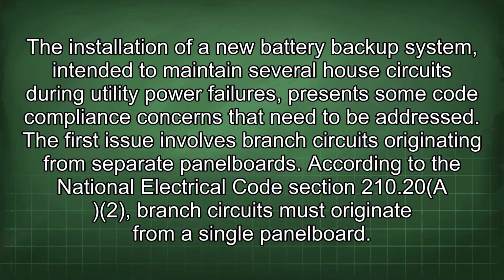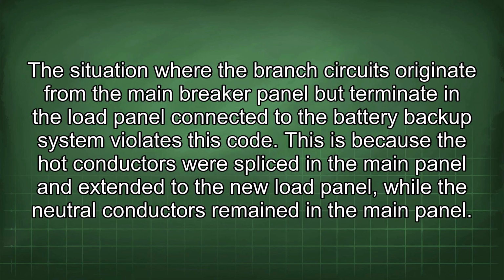The installation of a new battery backup system intended to maintain several house circuits during utility power failures presents some code compliance concerns that need to be addressed. First issue involves branch circuits originating from separate panel boards. According to the National Electrical Code Section 210.20, branch circuits must originate from a single panel board. The situation where the branch circuits originate from the main breaker panel but terminate in the load panel connected to the battery backup system violates this code.